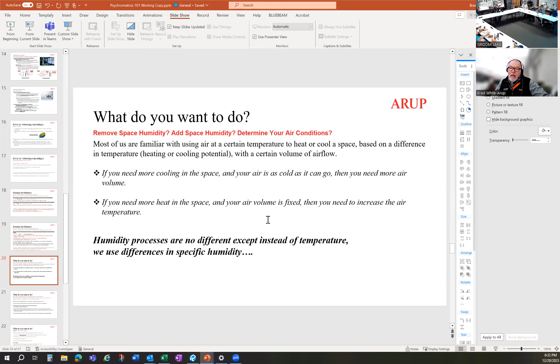And I'm not going to read these slides because that would just be cruel. Here's a sample of removing humidity from a space. You have your space, what things you need to know: your space design target conditions, your space discharge air conditions, difference between the two, your available airflow, I call it mass flow, but it's airflow, and your gains in BTUs or grains per pound per hour. And I give you here's a problem, and I'll let you take a look at these in the handouts as well.